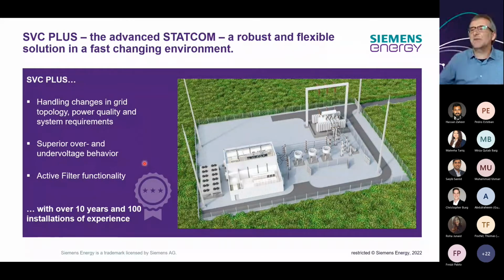The STATCOM itself has excellent under and over voltage behavior. It's a voltage source converter, so it's not depending on the voltage on the HV grid that much, and can still provide the necessary reactive power more or less independent from the grid.